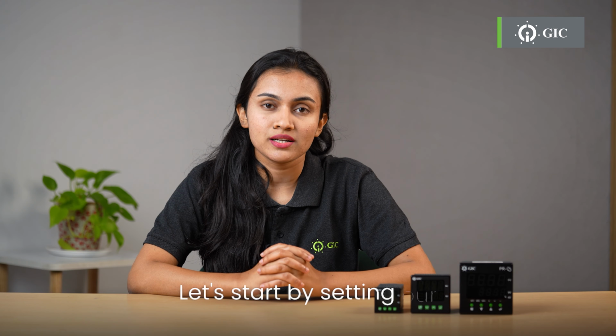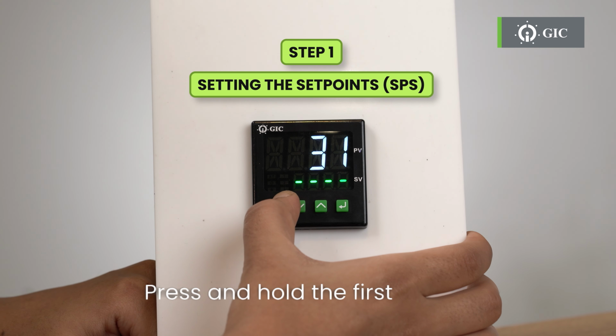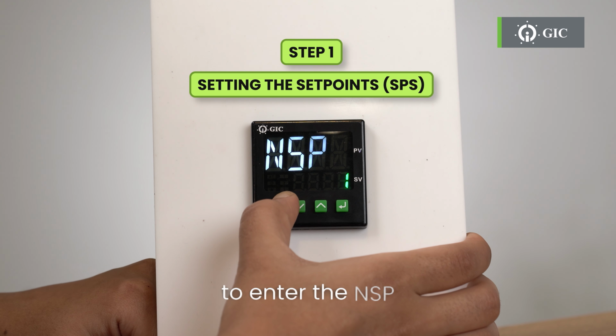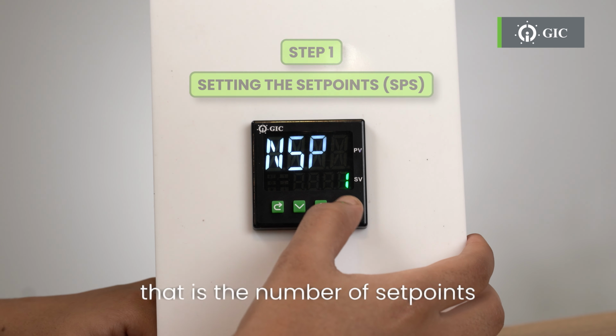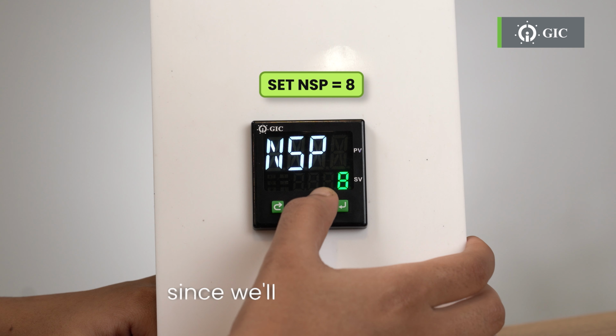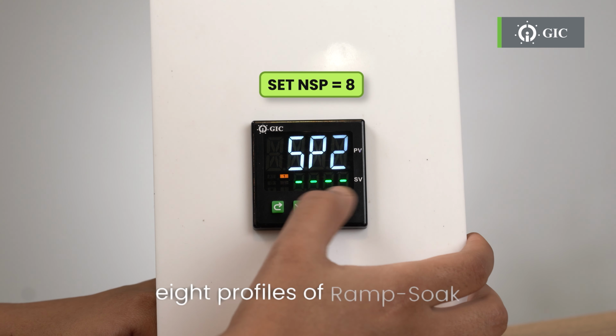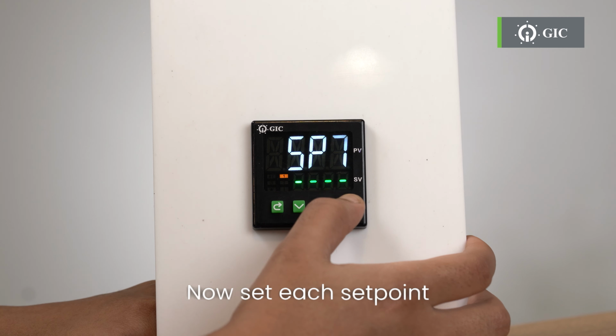Let's start by setting our set points for an 8-profile ramp soak sequence. Press and hold the first button for 2 seconds to enter the NSP, that is the number of set points. Set the NSP to 8 since we'll be using all the 8 profiles of ramp soak. Now, set each set point one by one.